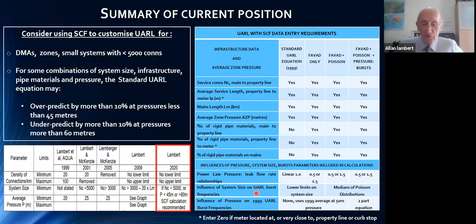There's now an optional methodology to predict the system correction factor to customize the UARL equation for any individual system, zone, or DMA. And optional checks to see if the UARL equation is likely to be out by more than plus or minus 10% are likely to be most relevant for small systems with less than 5,000 service connections, or systems outside the average pressure range of 45 to 60 meters.